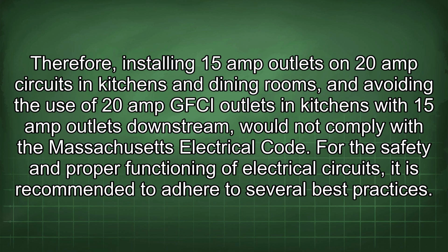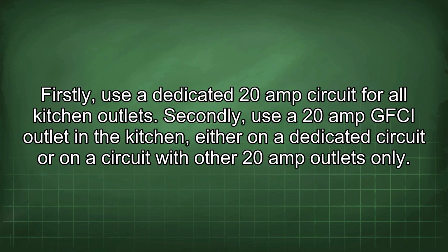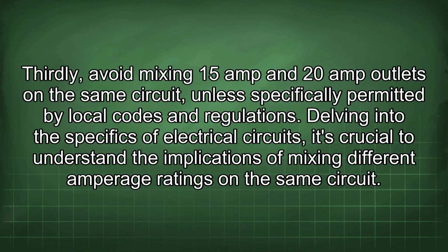For the safety and proper functioning of electrical circuits, it is recommended to adhere to several best practices. Firstly, use a dedicated 20 amp circuit for all kitchen outlets. Secondly, use a 20 amp GFCI outlet in the kitchen, either on a dedicated circuit or on a circuit with other 20 amp outlets only. Thirdly, avoid mixing 15 amp and 20 amp outlets in the same circuit unless specifically permitted by local codes and regulations.